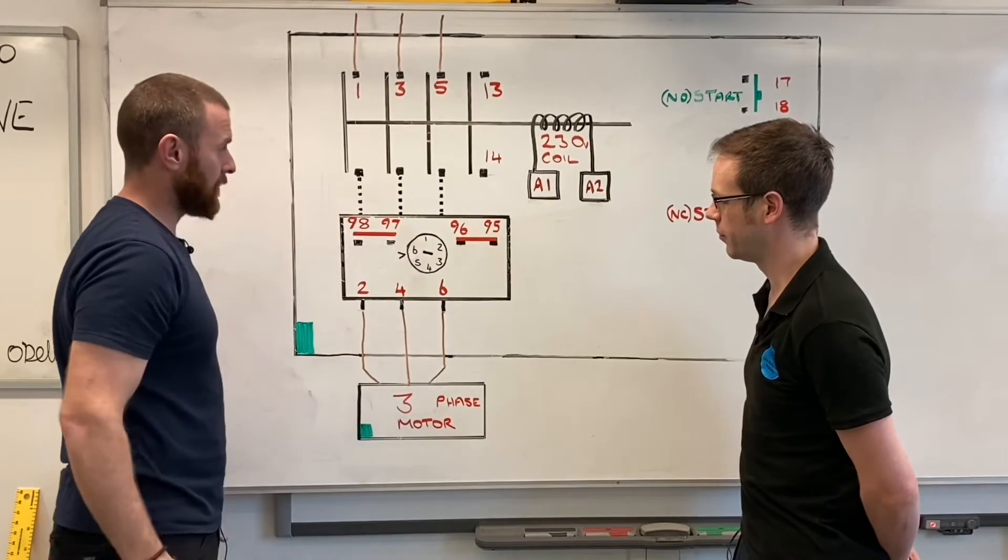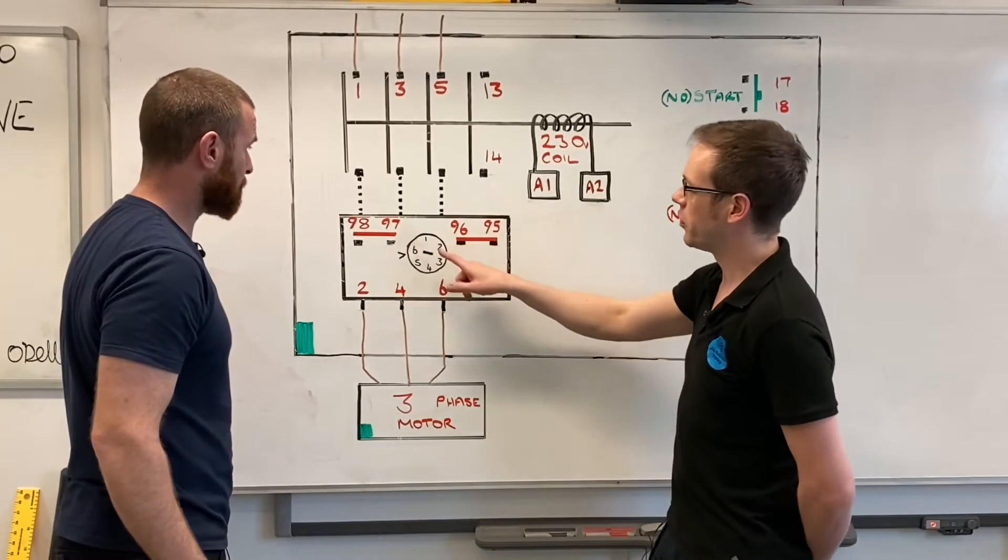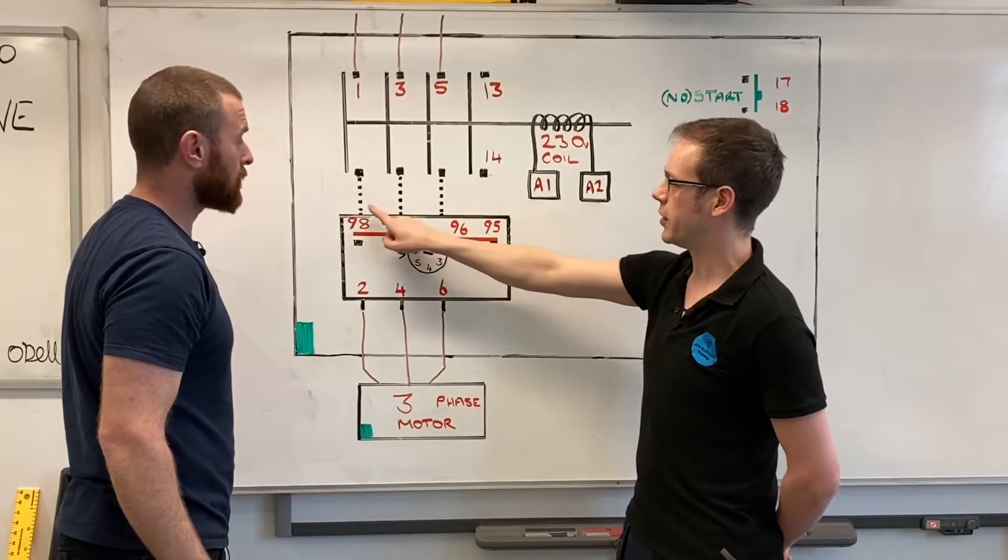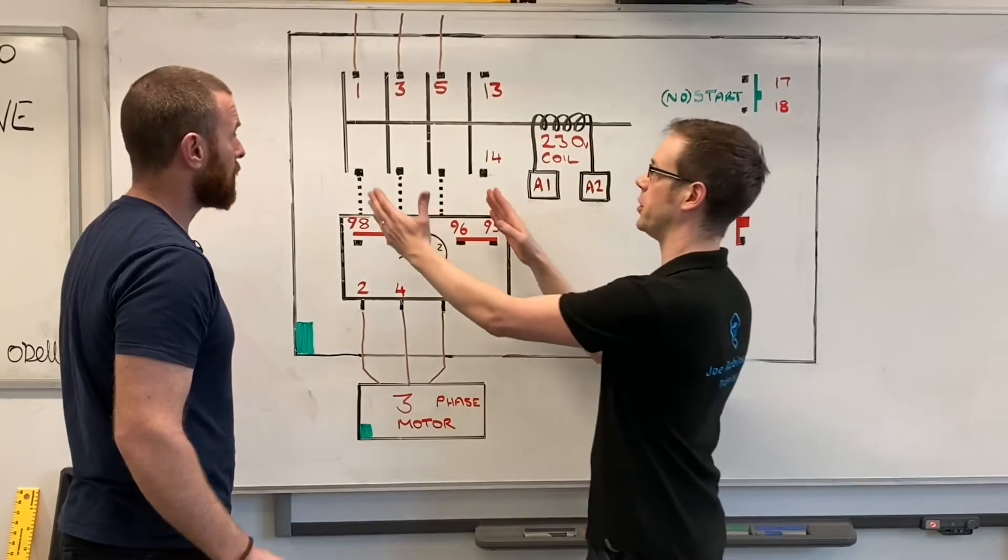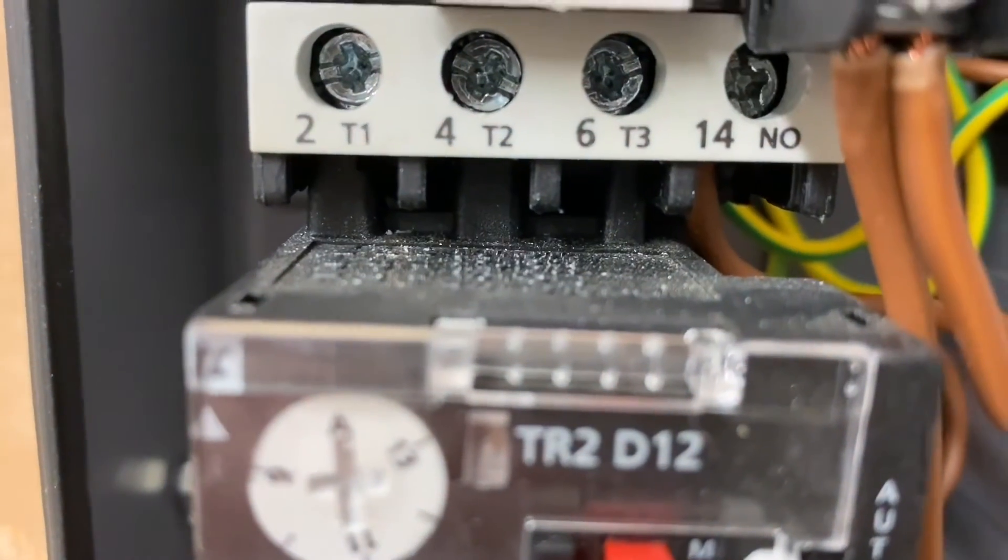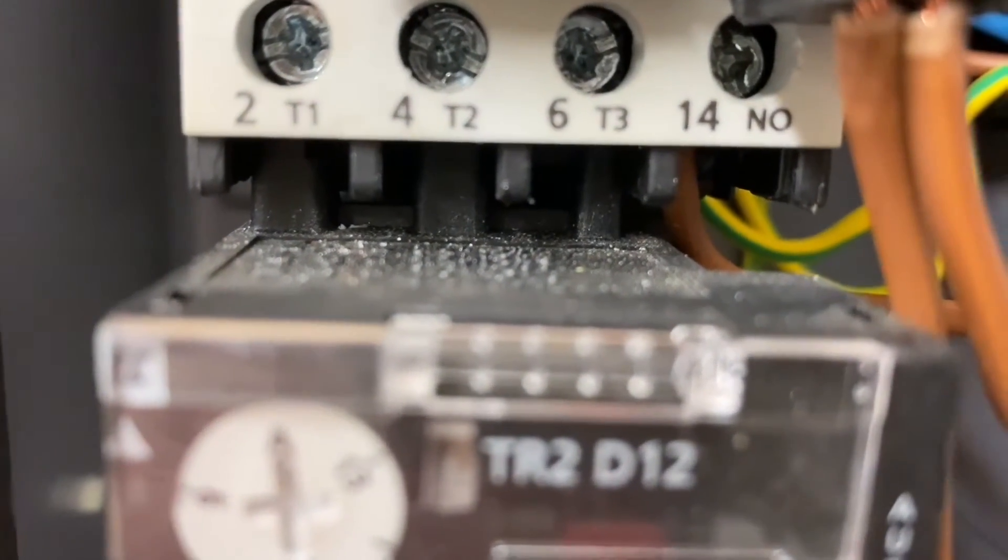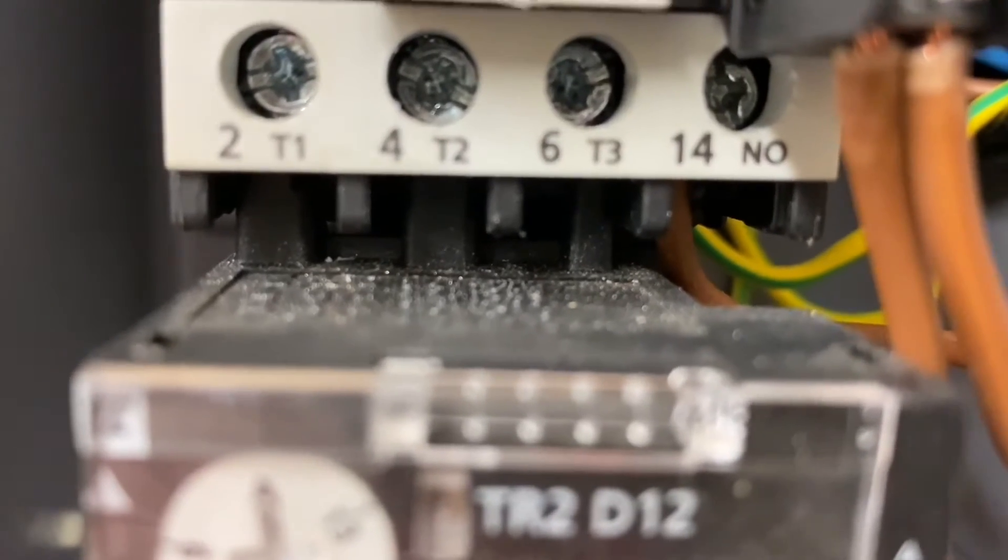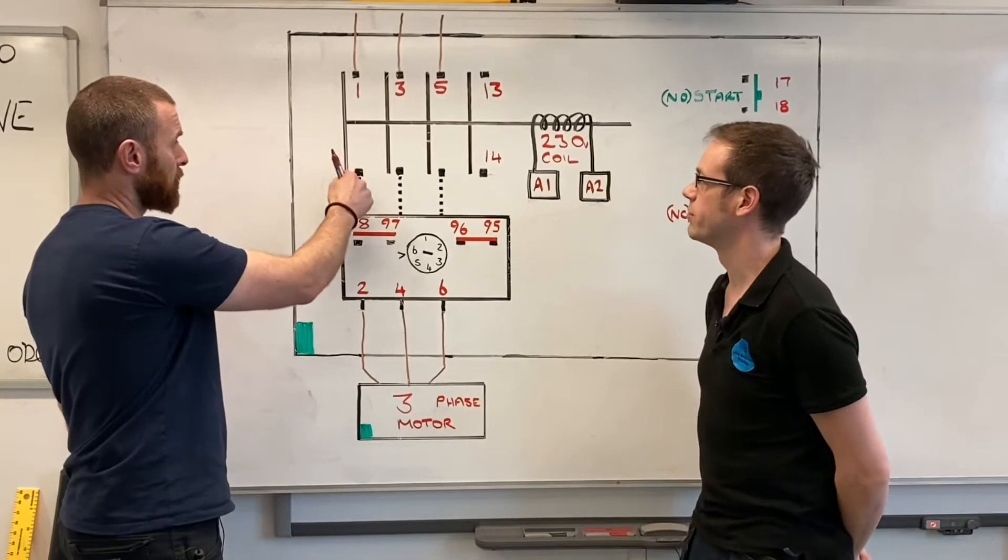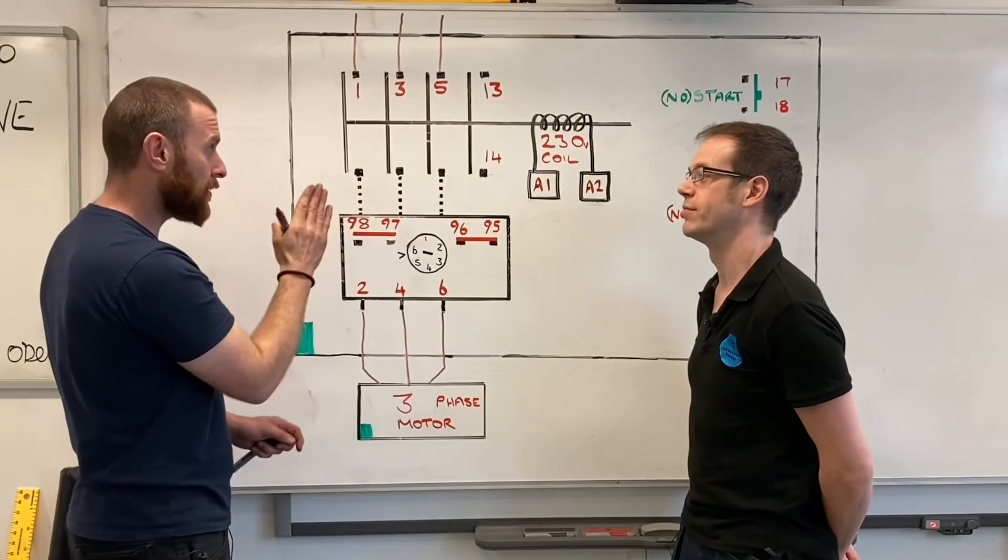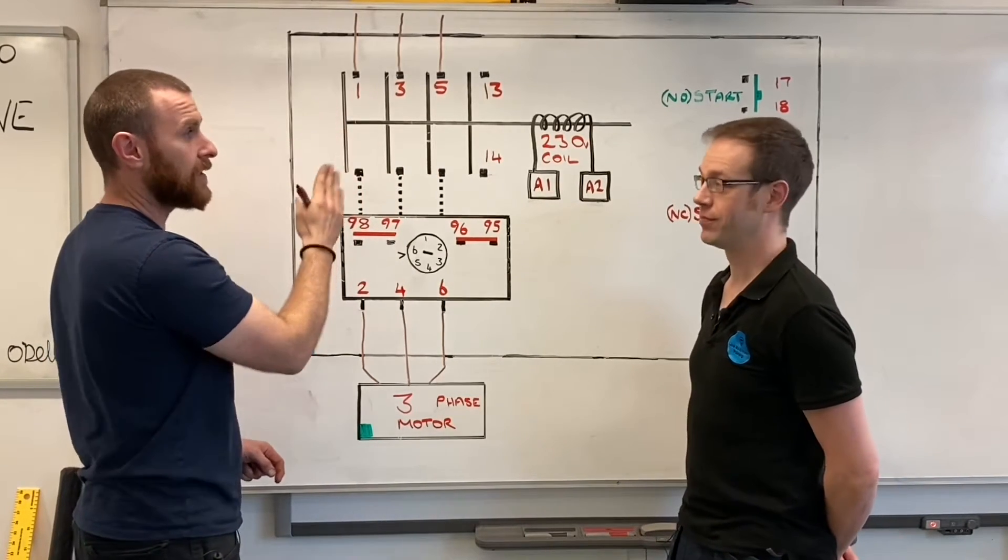Very nice, straight down to our three-phase motor. It's just worth noting as well on certain manufacturers of overload, you'll find that these pins move. You can sort of move them from one position to another depending on the physical size of the contactor. They click into different positions. If you are struggling to get it in, maybe one of the pins just needs moving over because with these types of terminals you can't go directly through the center, it's either left or right.